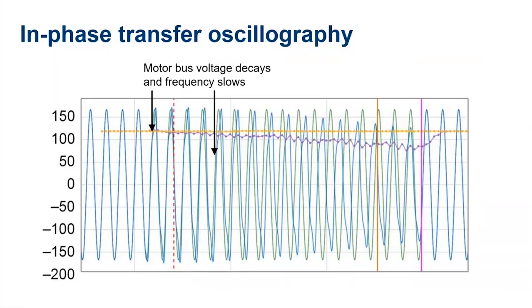Okay, so here we see the actual breaker open, but slightly before. After that, we get the 52A confirmation, but by that time we don't want to do an in-phase fast transfer, so we start measuring the phase, the frequency, and the rate of change in frequency. And when we determine that we can go to an in-phase at this point, we have to wait for the voltages to align again.